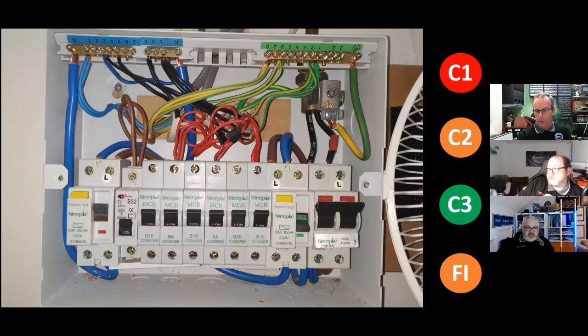I mean, I'm looking at 2 6-amp breakers with 5 circuits potentially in it. I'm looking at an AC split load board, and the connected use of the installation. Are we using intelligent stuff? Have we got inverter drive washing machines, the stuff that requires the A type? Is that a considerational factor? Realistically, it's screaming, shouting C3.